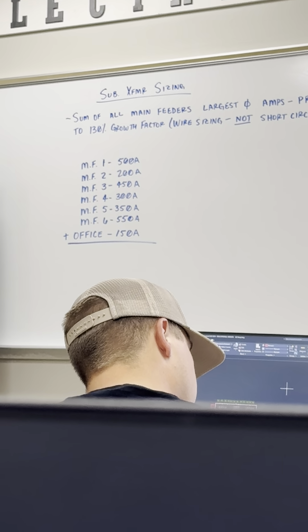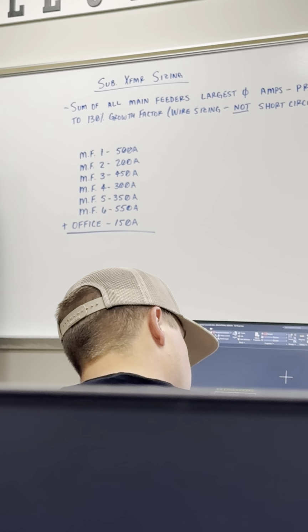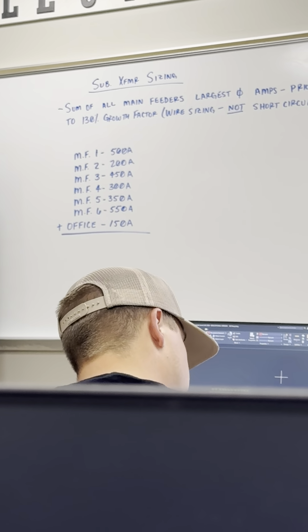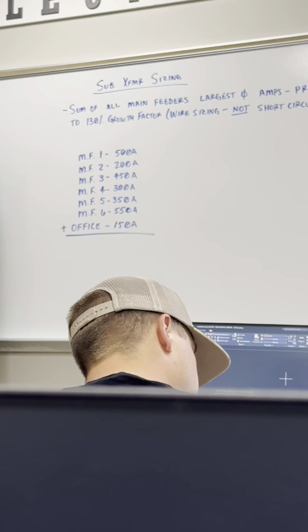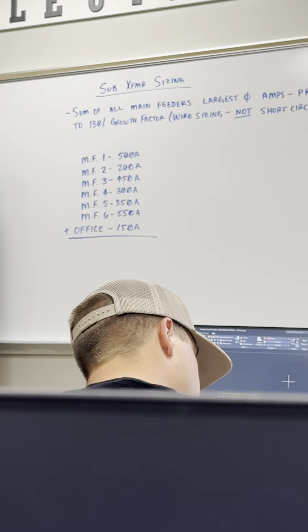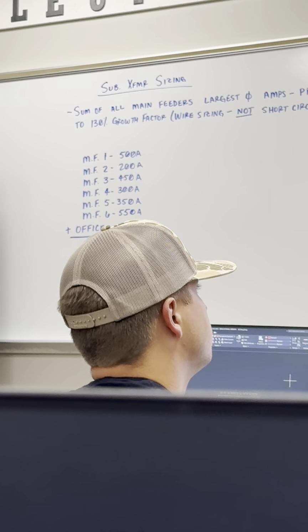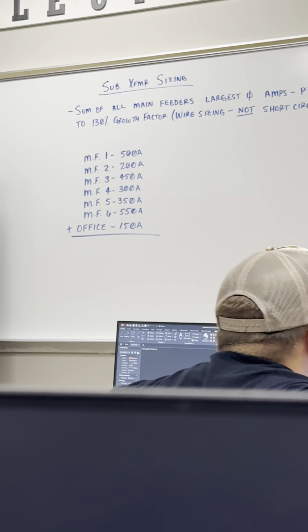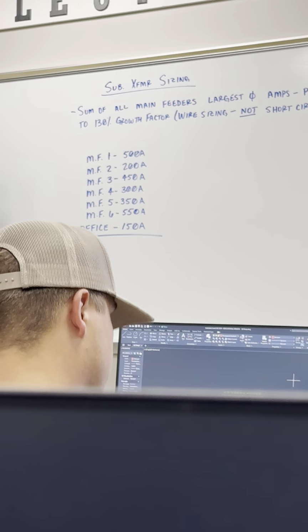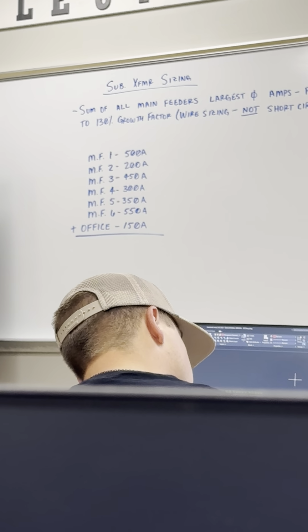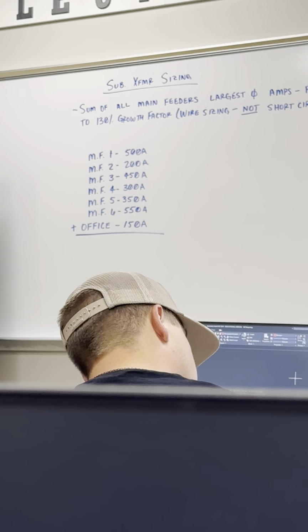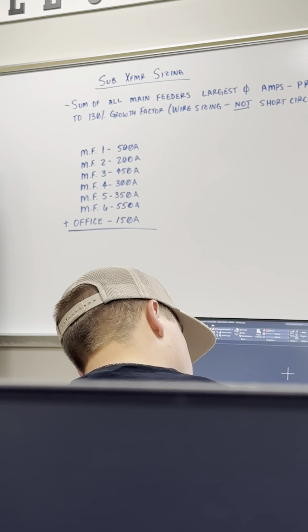And then office is the transformer for the office, right? Yes, the office transformer. So since that's going to be the same across all three phases, that's just whatever you calculated for that load, the transformer rated current. So, I'm going to add these up.